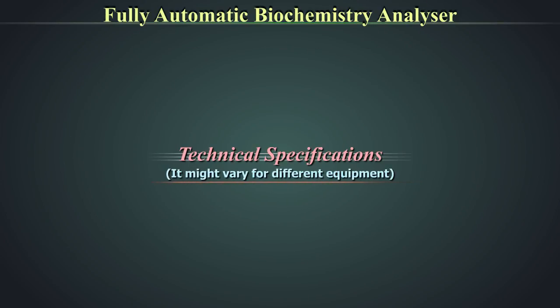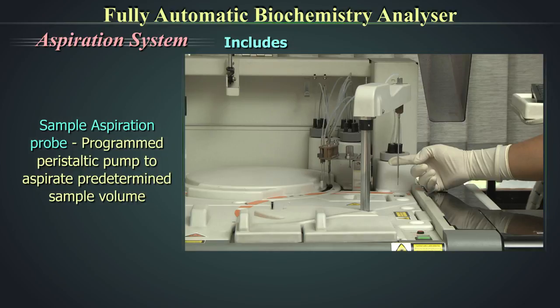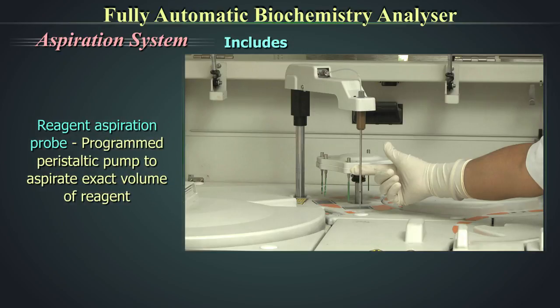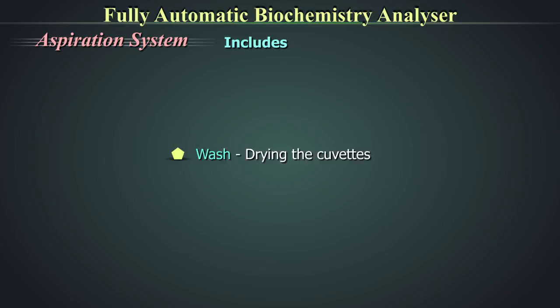Let us first understand the important technical systems of a biochemistry autoanalyzer. The aspiration system includes a sample aspiration probe with a programmed peristaltic pump to aspirate a predetermined sample volume, a reagent aspiration probe with a programmed peristaltic pump to aspirate an exact volume of reagent, wash nozzles for flow cell wash after every test sample, and air wash for drying the cuvettes after each sample.